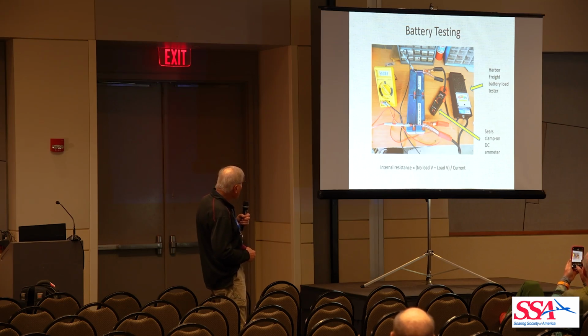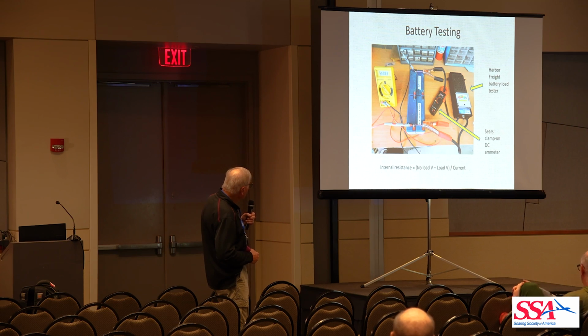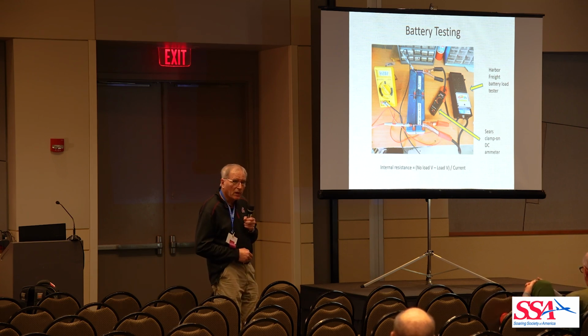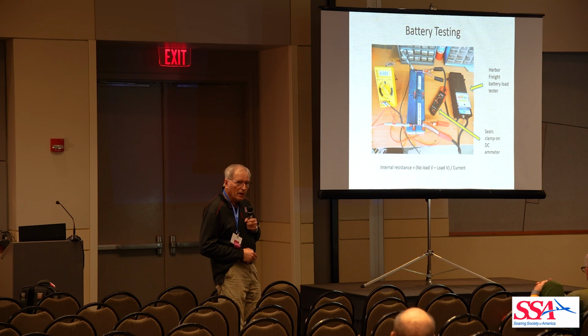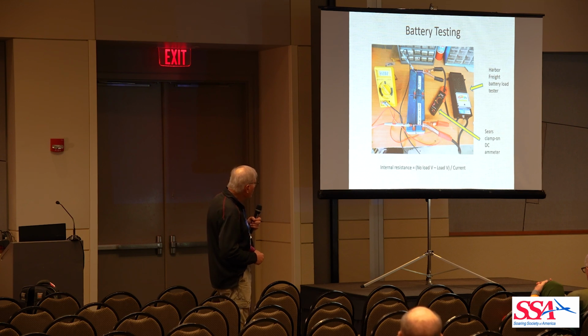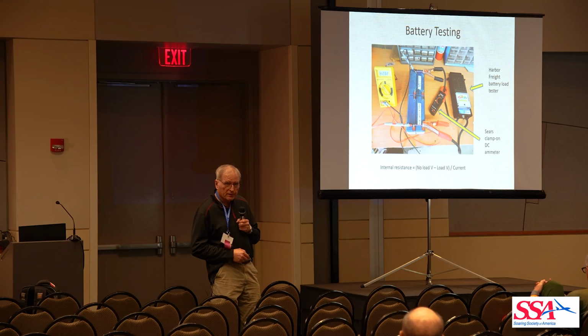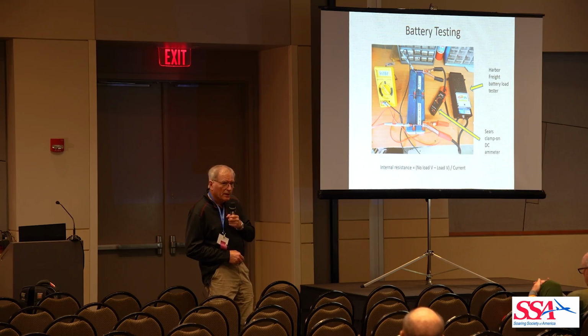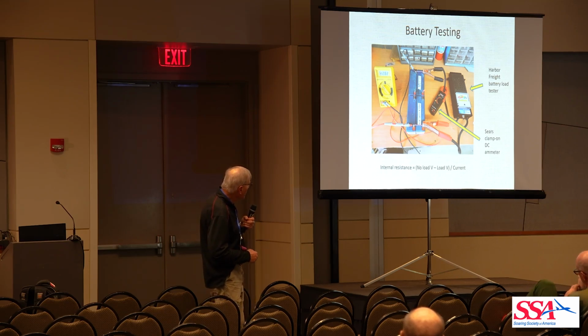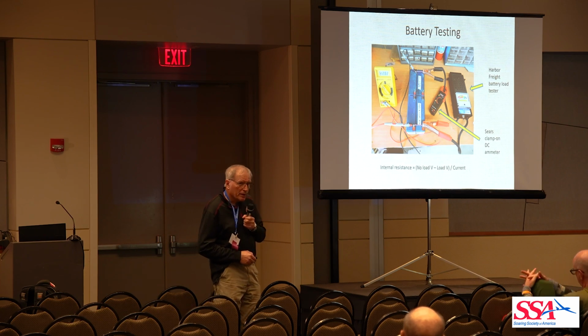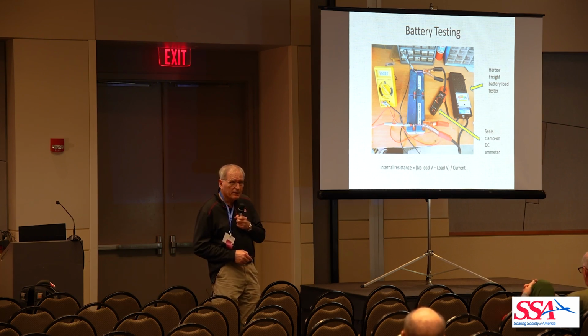And then a voltmeter. For internal resistance, you monitor the voltage before you apply the load, then monitor it after you apply the load, so you get a voltage drop. That voltage drop divided by the current is the internal battery resistance. On a new battery combination like this, it should be in the neighborhood of 10 milliohms, 10 thousandths of an ohm.